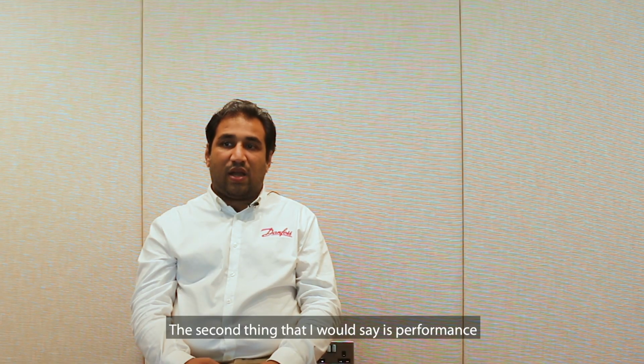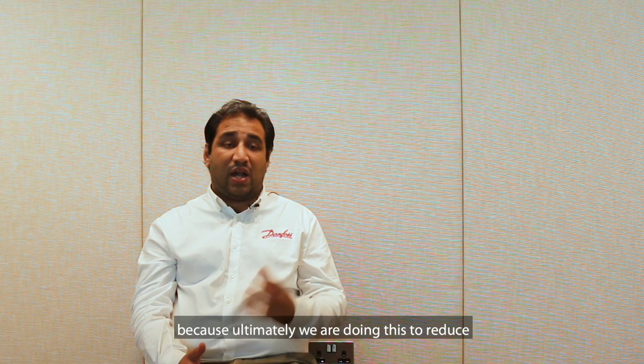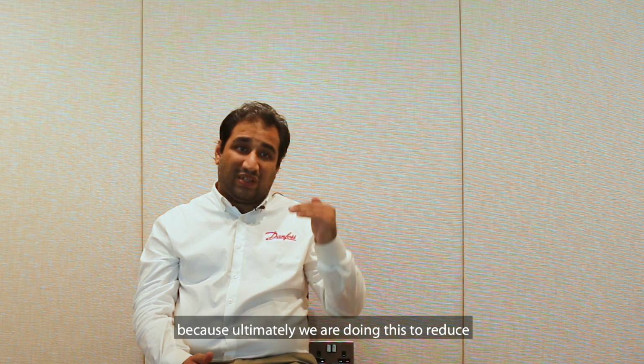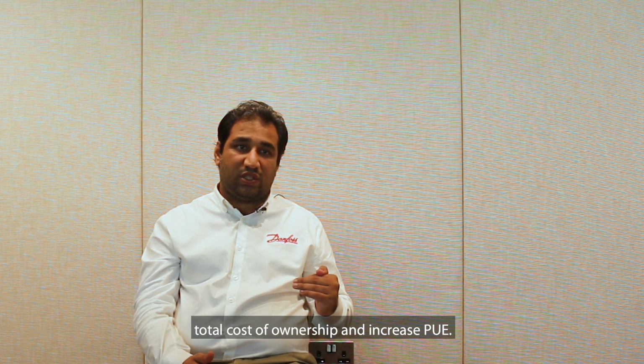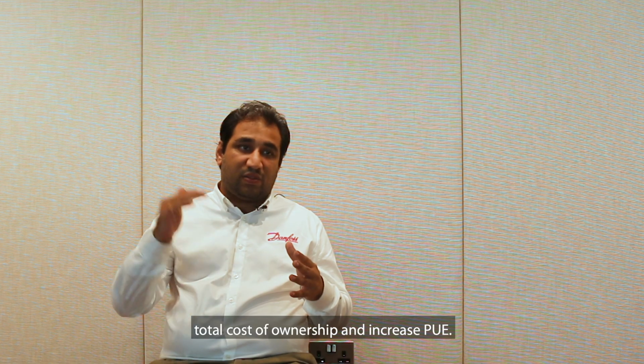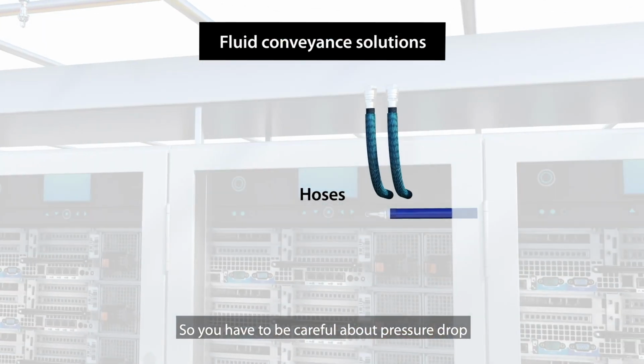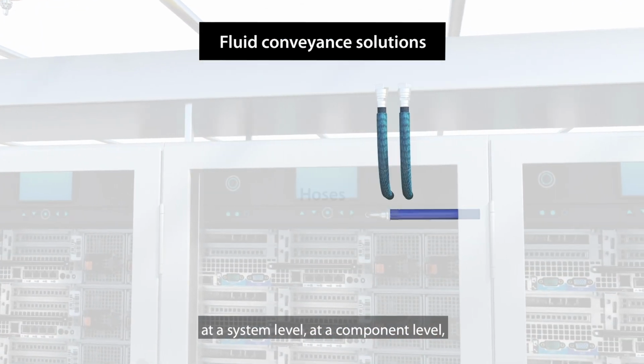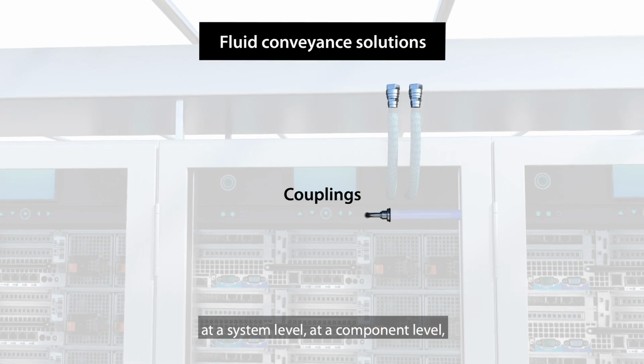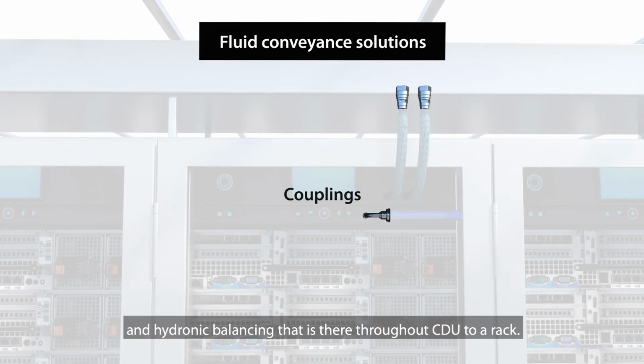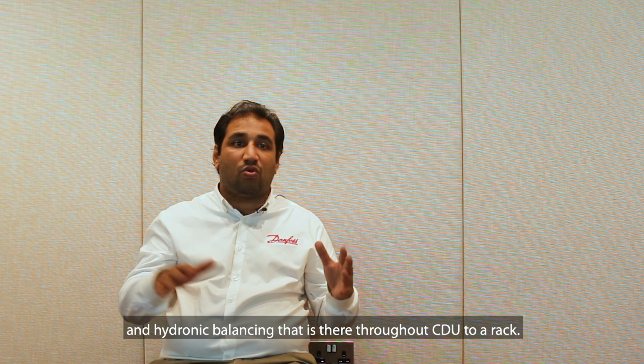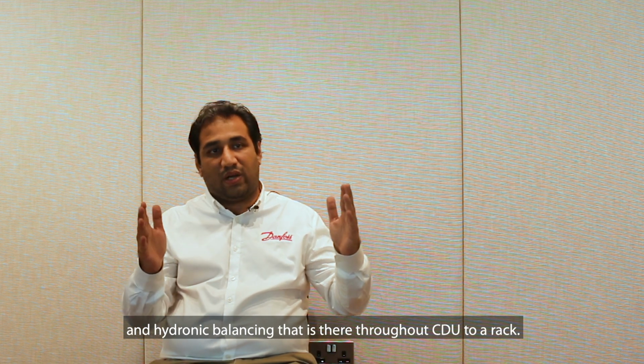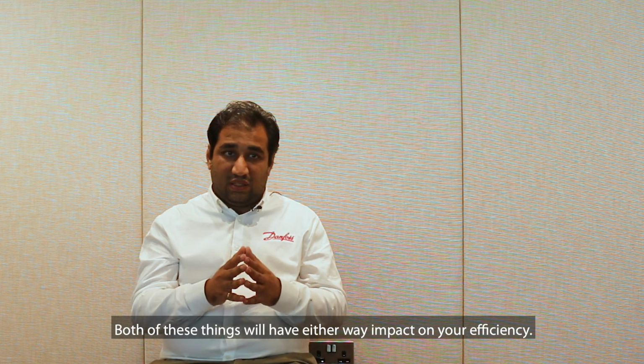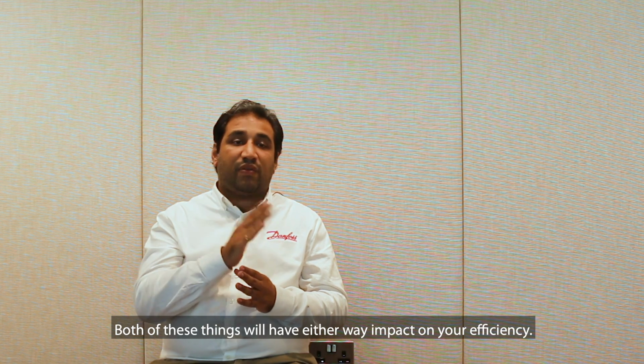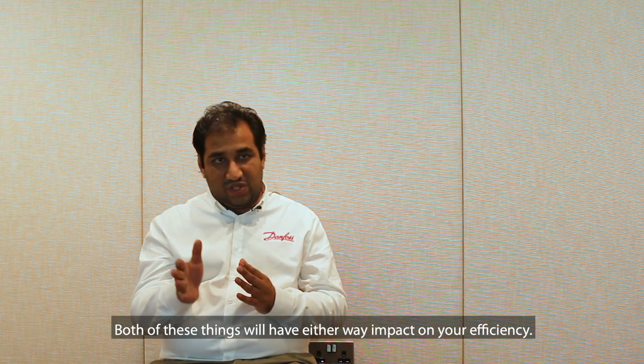The second thing is performance, because ultimately we're doing this to reduce total cost of ownership and increase PUE. You have to be careful about pressure drop at the system level and component level, and hydraulic balancing throughout the CDU to the rack. Both of these things impact efficiency either way.